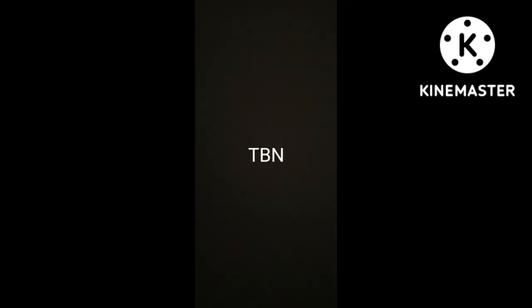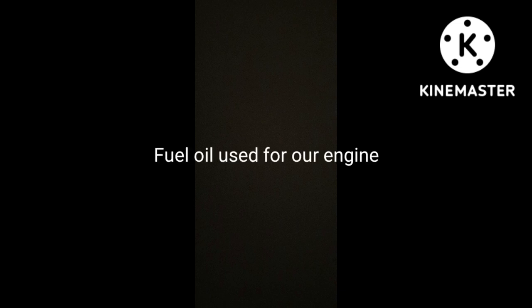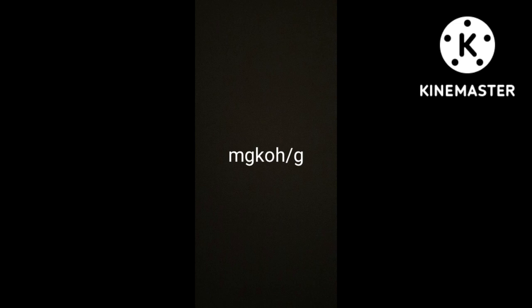Before we start, what is TBN? TBN means total base number. This is a property that measures oil's ability to neutralize acids formed during engine operation. So where do acids in our engine operation come from? The answer is from the fuel oil we use for our engines. TBN is expressed as mgKOH/g, or milligrams of potassium hydroxide per grams.